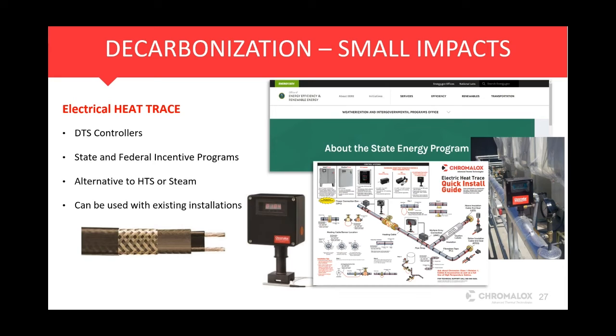A lot of larger heat trace systems installed today at power plants, oil and gas, or chemical facilities run on a central control system that kicks everything on or off at once, depending on freeze protection or process control. You can now retrofit with these units, which impacts your line loads by giving point of use control. It's really good for meeting some of these sustainability goals.